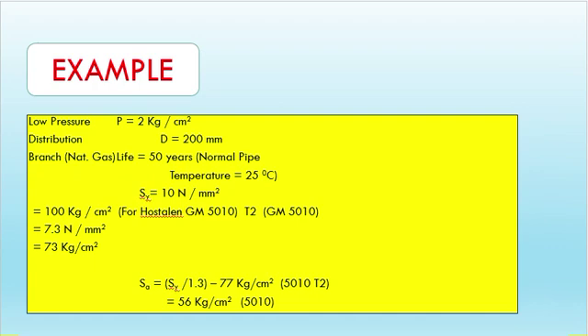An example for HDPE pipe: design pressure 2 kg/cm², diameter 200 mm, natural gas service, design life 50 years, normal pipe temperature 25°C, and SY = 10 N/mm². Using the formula T = PD / (2SA + P), you can easily calculate the HDPE pipe thickness.